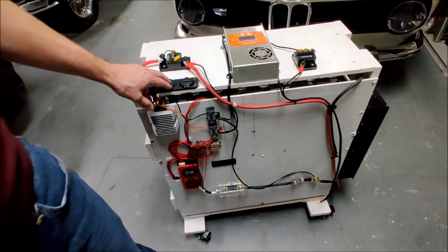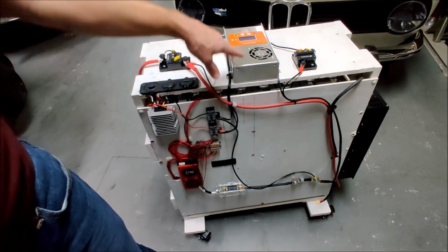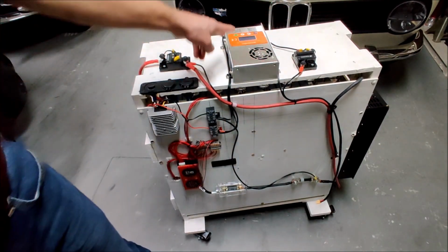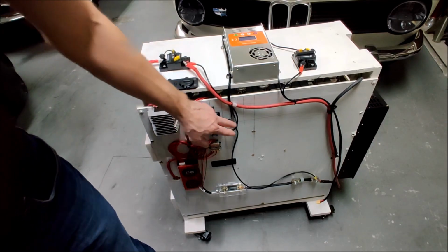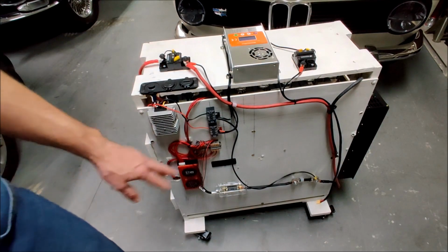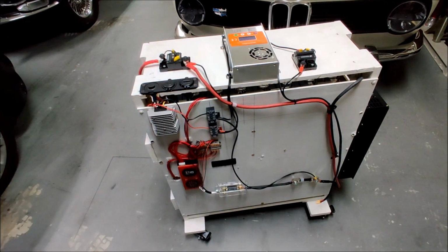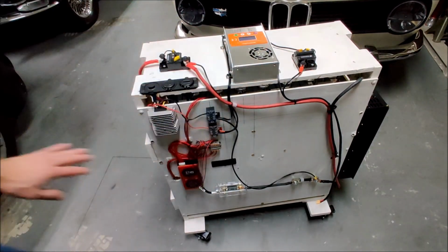It will also reverse read when the solar comes in. The solar will go into the bus bar and down back through the shunt and into the battery, so the meter will read reverse current as the incoming solar comes in.